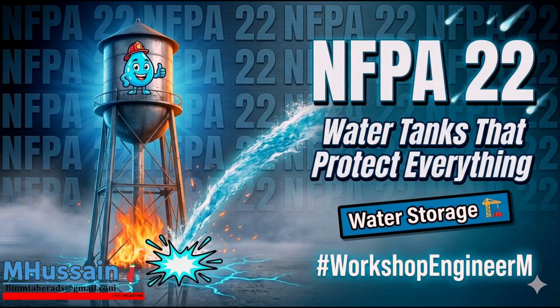Okay, let's move from static and pneumatic pressure into the realm of water and rapid motion. I want to dive deep into fluid dynamics, specifically Section 9.6.2.3. Vortexes and cavitation. Yes, we established earlier that a vortex can destroy a pump. But let's break down the actual fluid mechanics of why a whirlpool in a tank is so lethal to a system. When a massive centrifugal fire pump activates, it generates a tremendous velocity at the suction inlet pipe, which is usually located at the bottom of the tank.